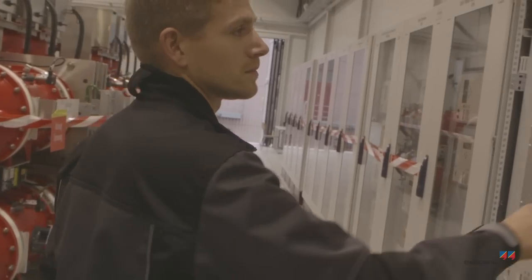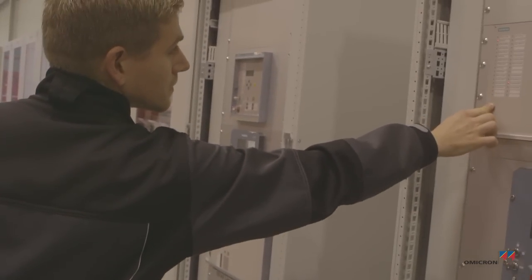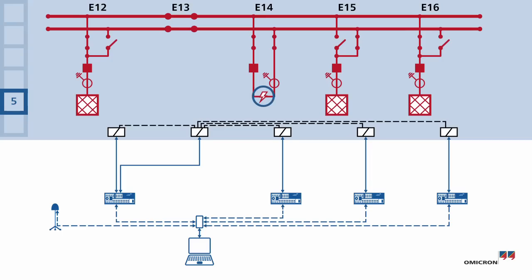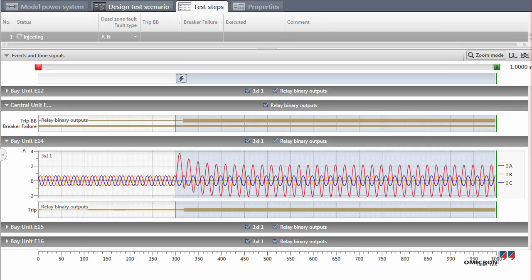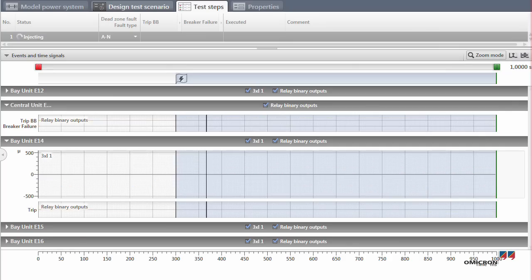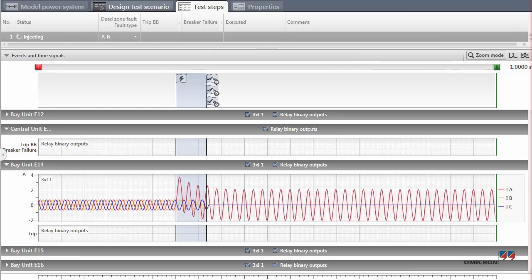When Florian triggers a fault between the CT and the circuit breaker in the coupling field, RelaySimTest applies its iterative closed loop feature once again.